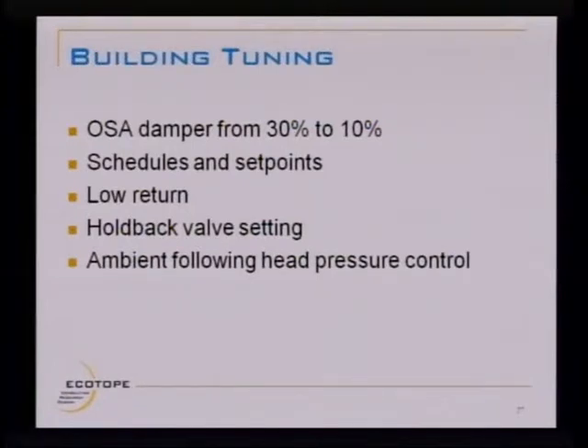We discovered in commissioning that the holdback valve had not been installed. So we got it installed, but the guy had come back and opened it up all the way so that his refrigeration system could float down to lower condensing temperatures. And we didn't figure that out until we had a few months of data on how much gas was being used, and we were wondering, why are we using so much gas still? For this reason.